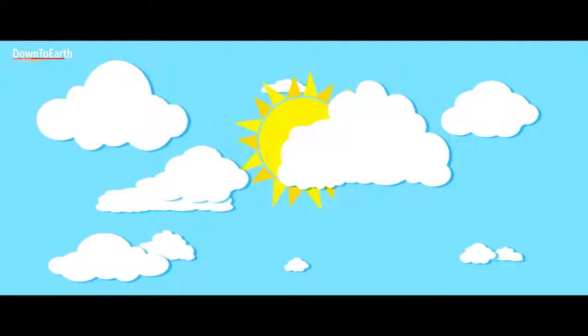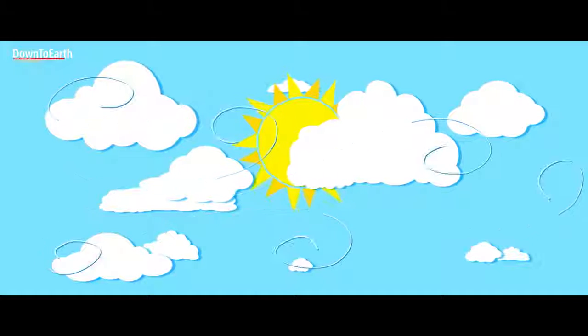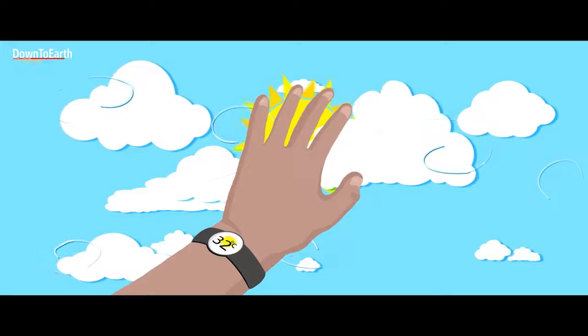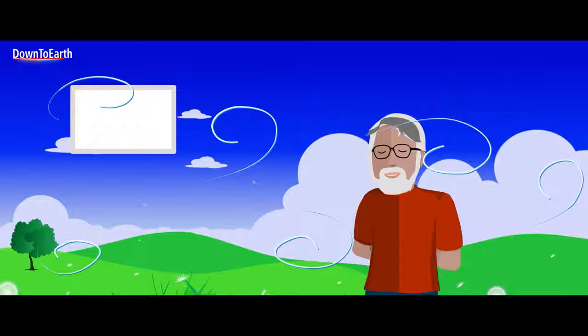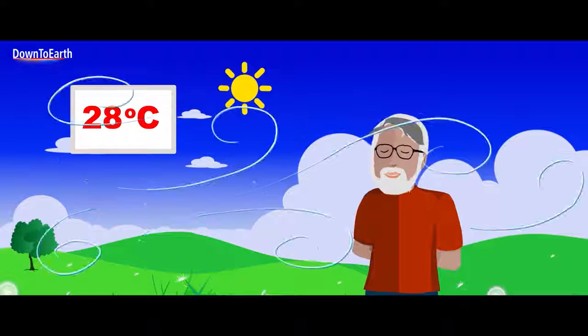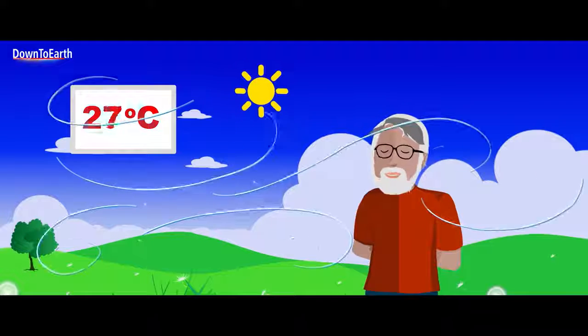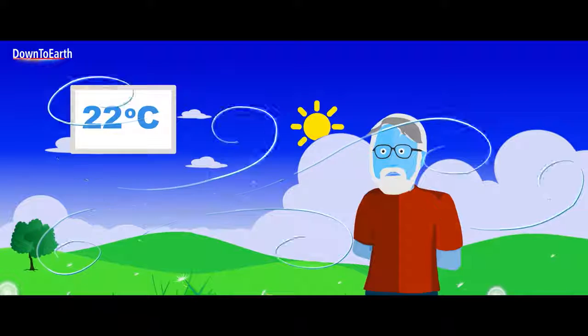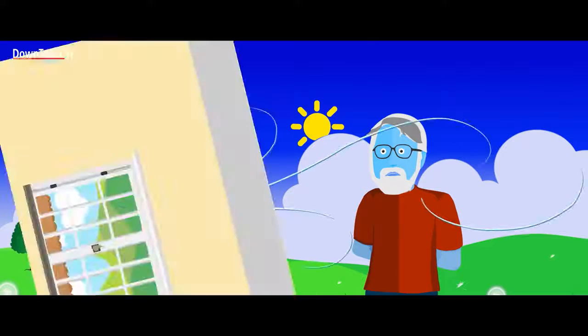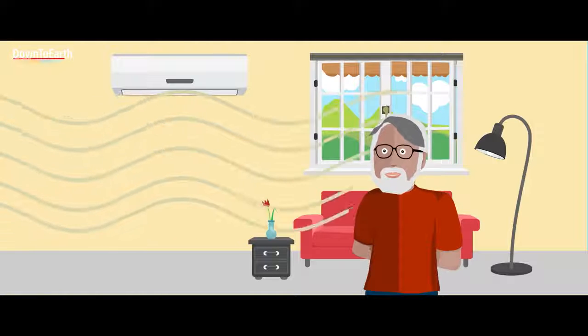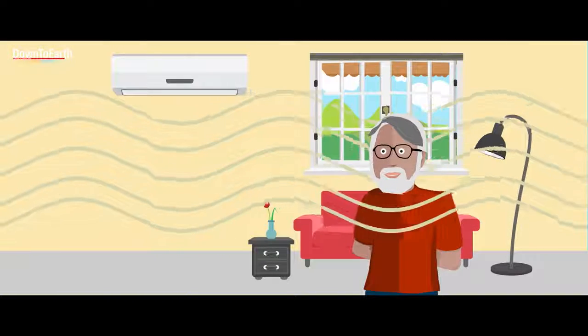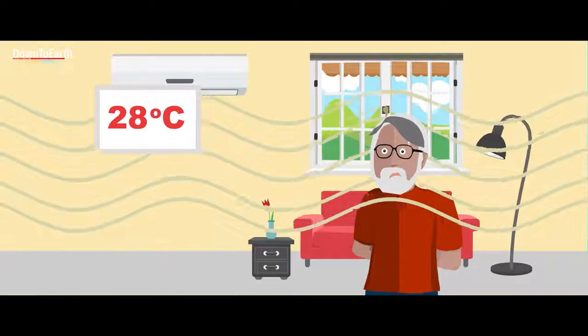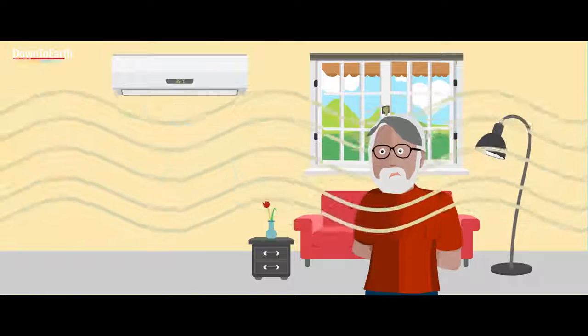Keeping this principle in mind, in warm climates we find the breeze to be comforting when the air temperature is below our skin temperature or less than 32 degrees centigrade. When the air temperature goes above 26 degrees centigrade, we like a gentle breeze. But when the breeze is cooler than that, it is no longer pleasant. It becomes a chilling draught which we would avoid. On the other hand, if the air is already humid and won't evaporate moisture from the skin, even 28 degrees centigrade begins to feel uncomfortable. We start sweating. That is when we resort to air conditioning.